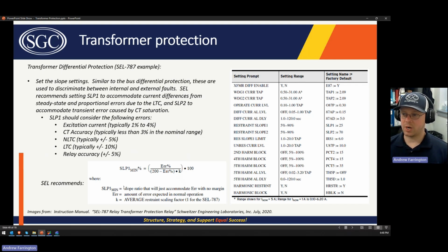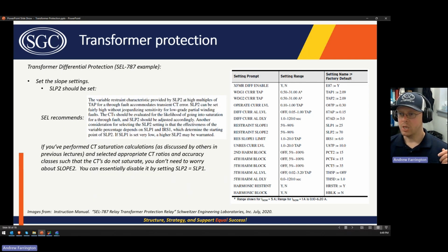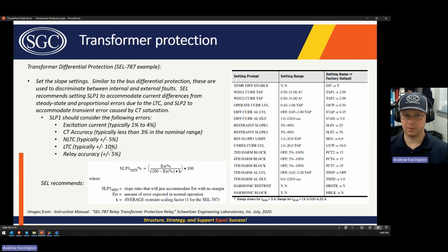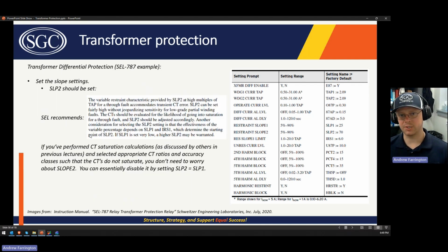So Schweitzer recommends a minimum slope based on this equation. I'm not going to go through how you'd actually calculate that. You just look at the relay manual for your relay and you determine your slope based on that. But I just wanted to give you a general sense for what that's intending to cover and why you have the different slopes. Slope 2 is to account for transient errors, right? These are things that are not necessarily continuous, but they're long-term things, right? The LTC is going to change all around. It's not a permanent inaccuracy, say, because it may change from time to time, but it's consistent. It's not a transient issue. Slope 2 is to account for transient issues like CT saturation.